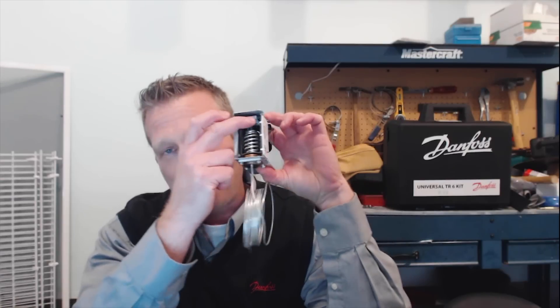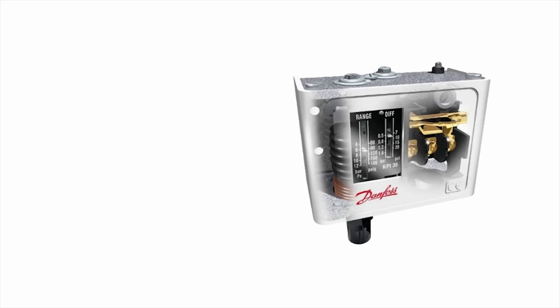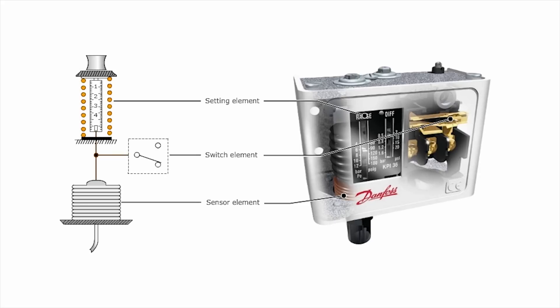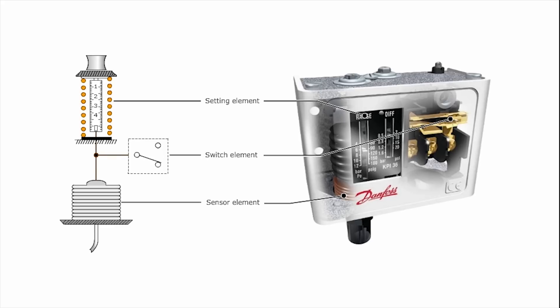If we take a look at this control you will see there's a set of bellows right here, and on top of that there is a spring opposing those bellows, and in between there's a common linkage attached to a set of contacts. So if the pressure rises — the temperature rises and the pressure rises — the bellows are going to expand against that spring and move those sets of contacts. They can open on a rise in temperature and close on a fall in temperature, or vice versa.